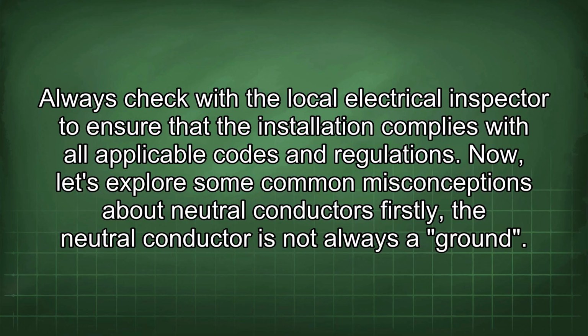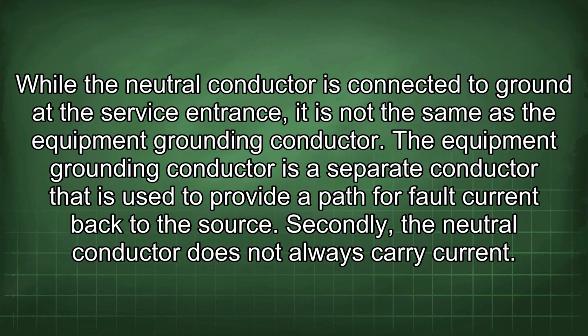Firstly, the neutral conductor is not always a ground. While the neutral conductor is connected to ground at the service entrance, it is not the same as the equipment grounding conductor. The equipment grounding conductor is a separate conductor that is used to provide a path for fault current back to the source. Secondly, a neutral conductor does not always carry current.